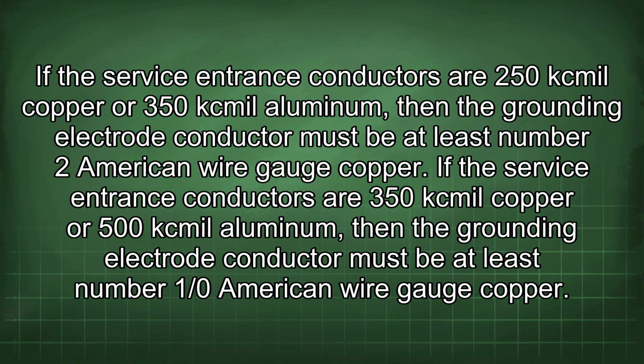If the service entrance conductors are 250 kcmil copper or 350 kcmil aluminum, then the grounding electrode conductor must be at least number 2 American wire gauge copper. If the service entrance conductors are 350 kcmil copper or 500 kcmil aluminum, then the grounding electrode conductor must be at least number 1/0 American wire gauge copper.